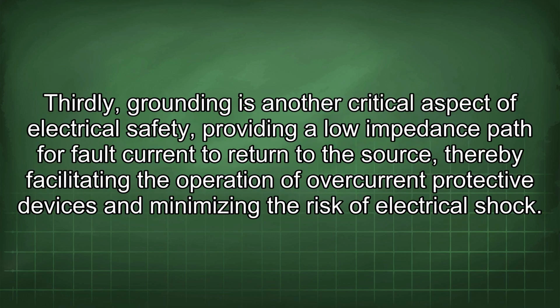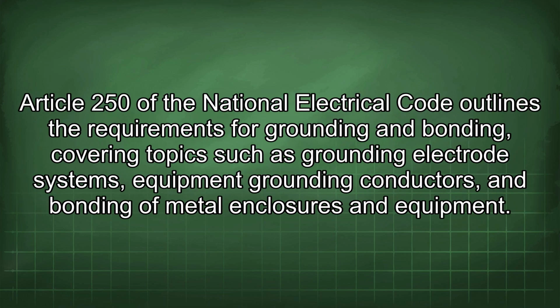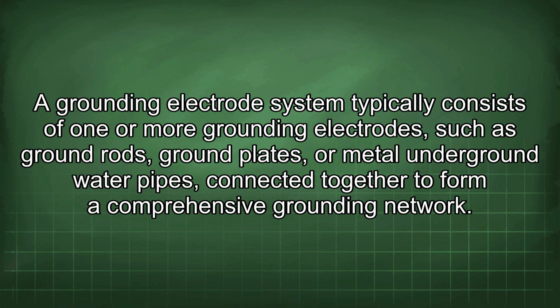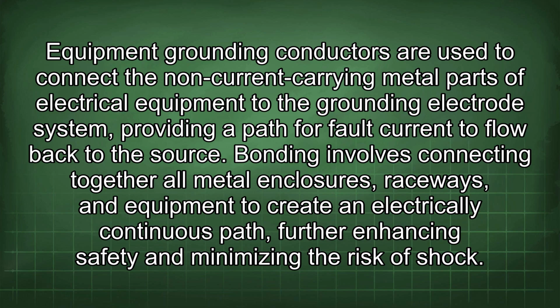Thirdly, grounding is another critical aspect of electrical safety, providing a low impedance path for fault current to return to the source, thereby facilitating the operation of overcurrent protective devices and minimizing the risk of electrical shock. Article 250 of the National Electrical Code outlines the requirements for grounding and bonding, covering topics such as grounding electrode systems, equipment grounding conductors, and bonding of metal enclosures and equipment. A grounding electrode system typically consists of one or more grounding electrodes, such as ground rods, ground plates, or metal underground water pipes, connected together to form a comprehensive grounding network. Equipment grounding conductors are used to connect the non-current carrying metal parts of electrical equipment to the grounding electrode system, providing a path for fault current to flow back to the source. Bonding involves connecting together all metal enclosures, raceways, and equipment to create an electrically continuous path, further enhancing safety and minimizing the risk of shock.